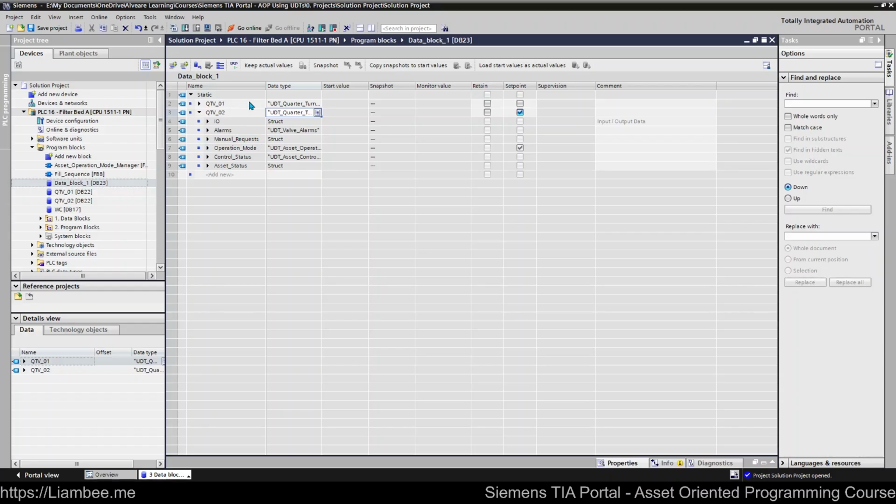Whilst a lot of things are symbolically referenced and it shouldn't affect SCADA or HMIs, depending on how you've set up your project, you might need to pass all of your tags back to your HMI or SCADA and readdress them, because the actual memory offset is different. That's not that bad.